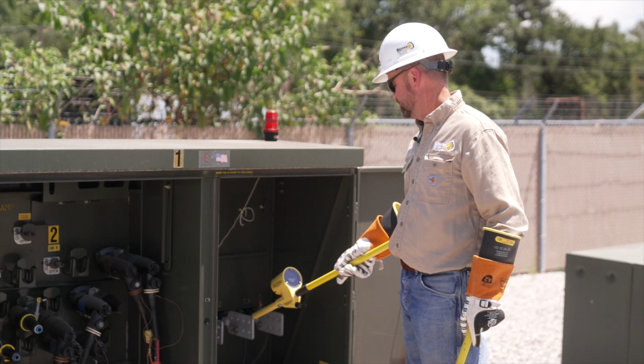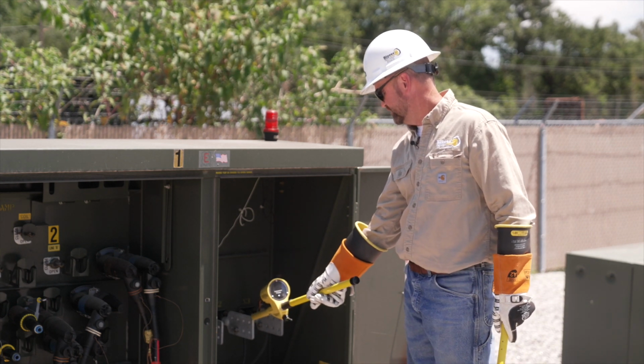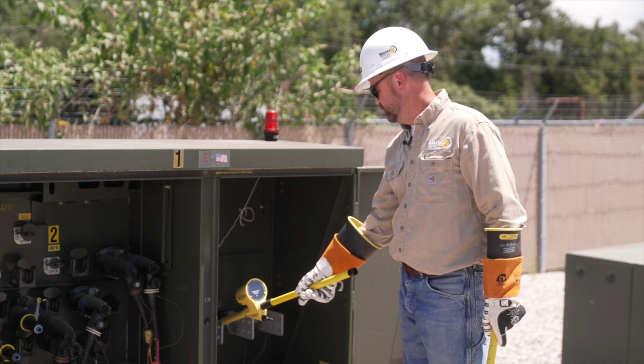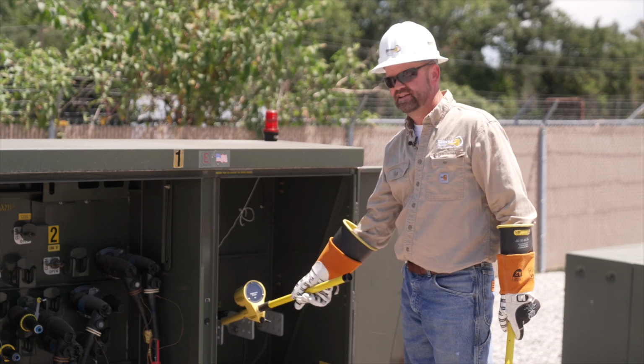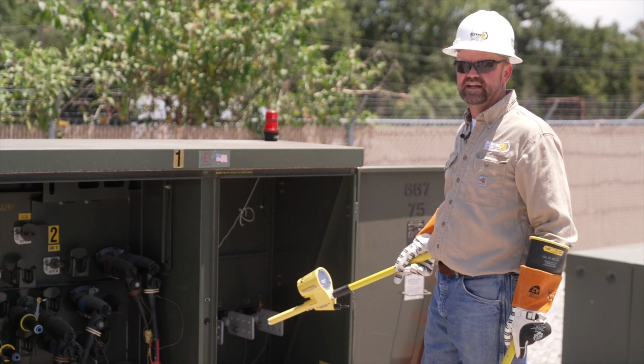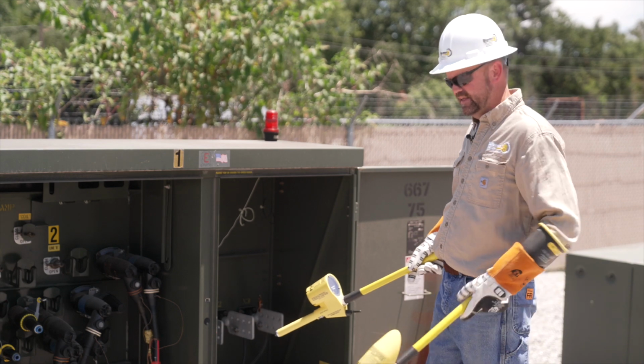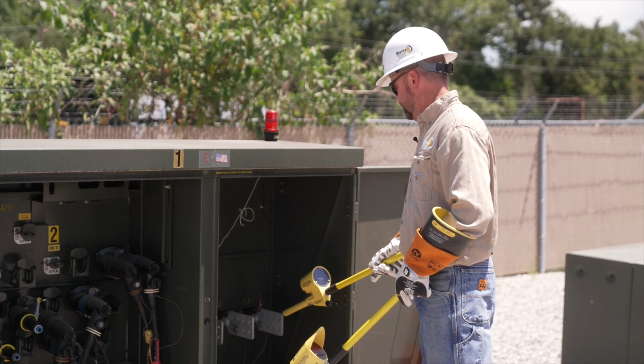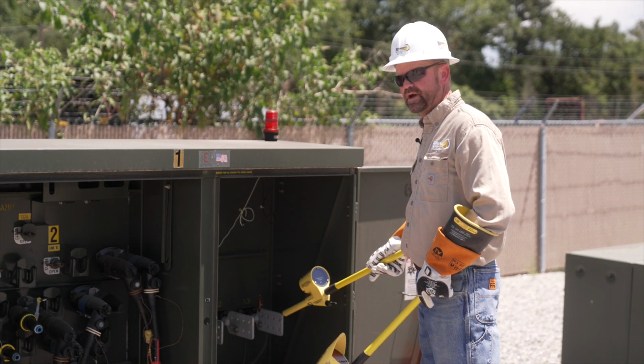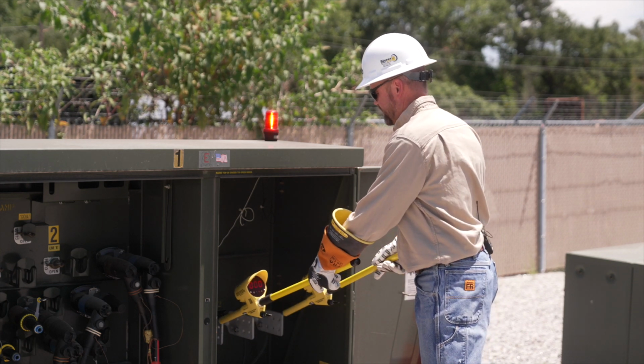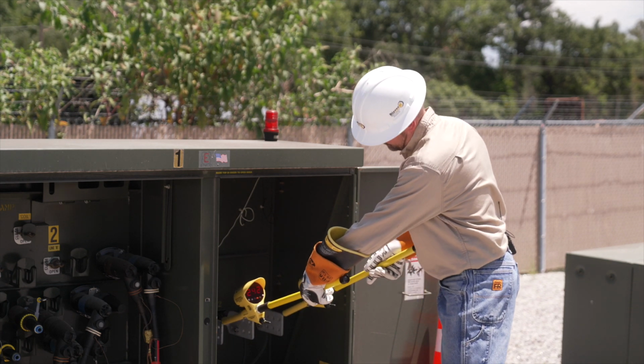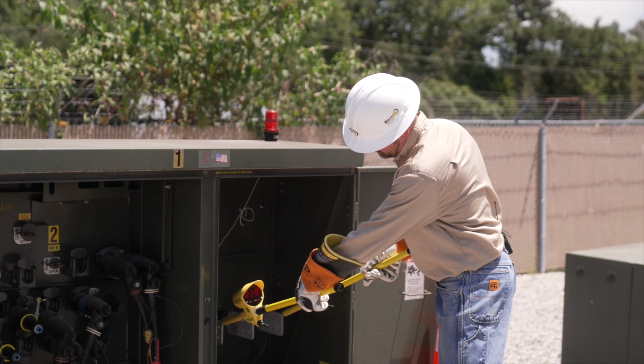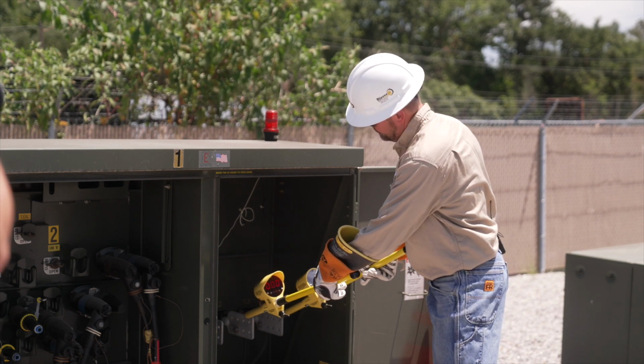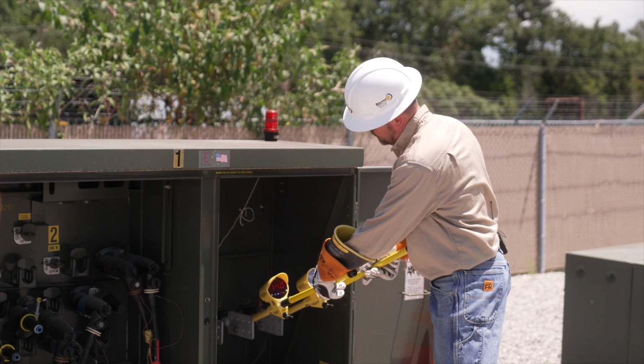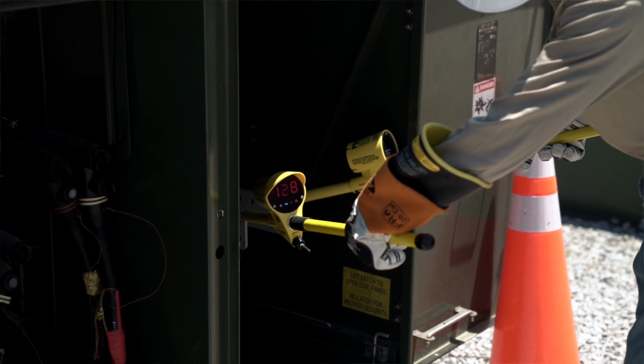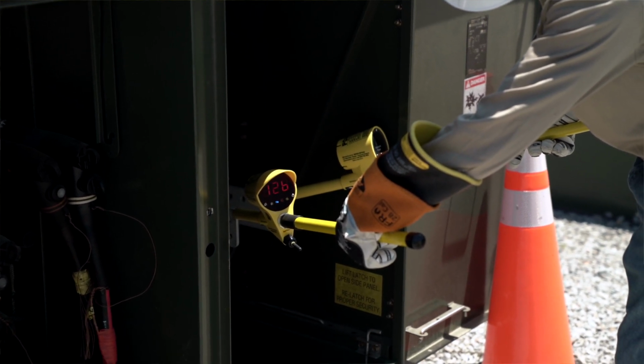So I can touch my X2 bushing, I get a white light. I can touch my X1 bushing and I get a white light. So I know all three of these secondaries are in fact hot. Now I can begin phasing. Again, I'll touch the X3 bushing with my reference probe. I'll touch the X1 bushing with my meter probe. There I have my near 240 degrees and a red light. I touch the X2. I have my blue light and my near 120 degrees.